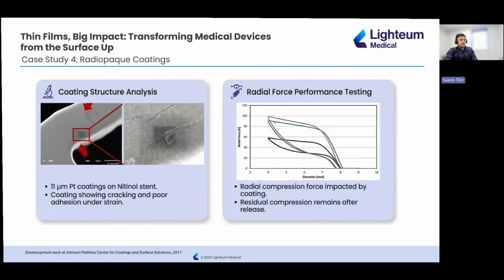Even more concerning, if you look at the chart on the right, mechanical testing showed that the presence of the thin platinum layer actually changed the radial force behavior of the stent. After compression, it didn't fully recover, and it required more force to close. So the coating solved the visibility problem, but broke the mechanical performance of the device.